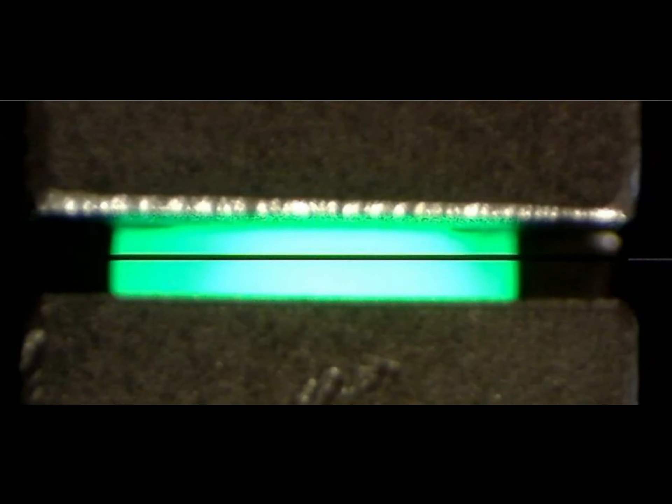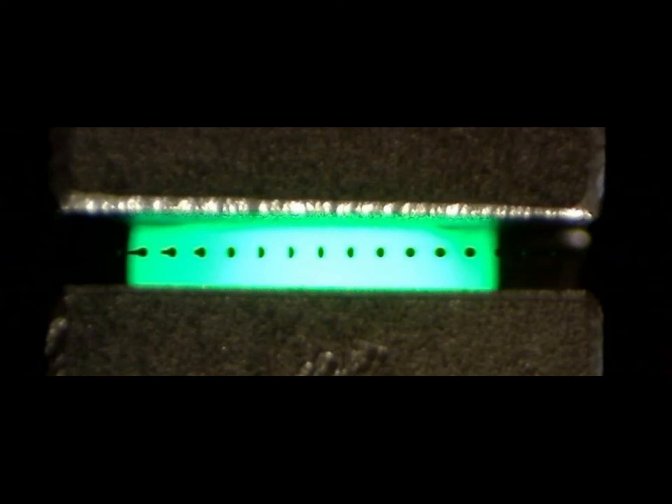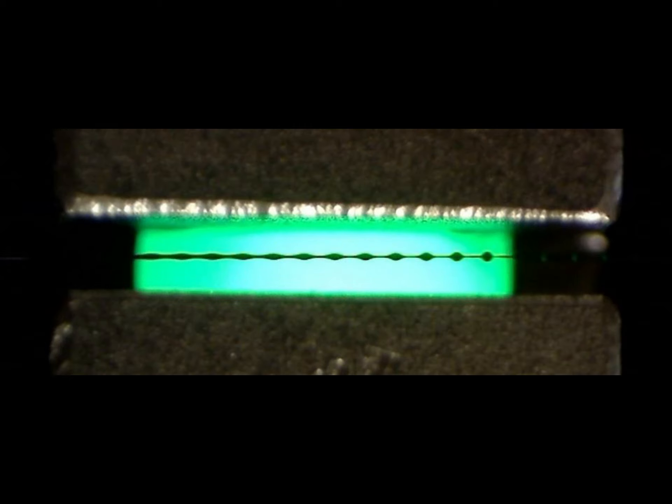So in this first example, when you look with an eyeglass down on that green LED, this is what you're going to see. So this first example is an example of no drop breakup whatsoever. So there's no voltage getting onto the drop generator causing the droplets. This second one, the modulation voltage is set too low. And you can see that the pear drop type droplets, there's only a couple there before it gets to the full formed. This example, this is too high.